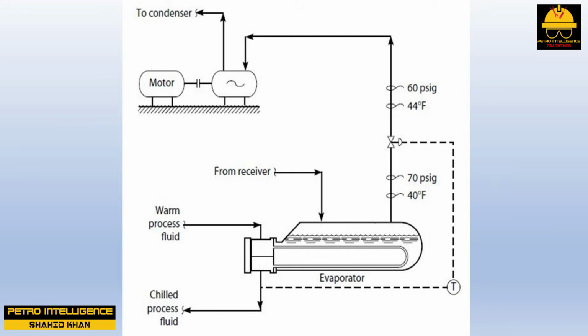Correct. But the price we pay is a hot home. How about the compressor discharge pressure? What is this controlled by? Answer is the condenser. The compressor discharge pressure has nothing whatsoever to do with the compressor.